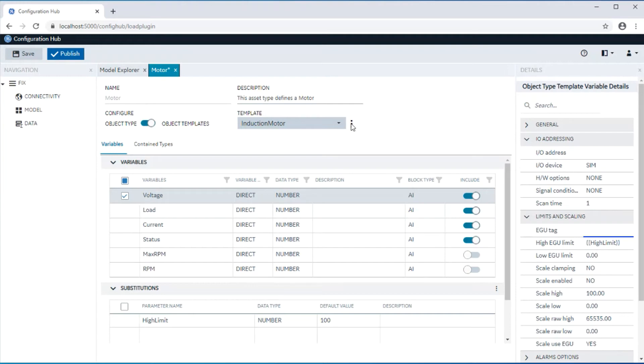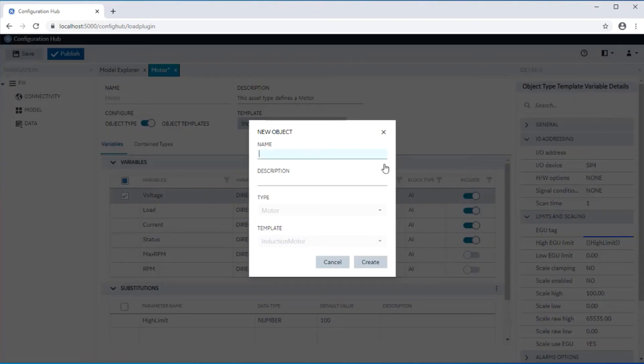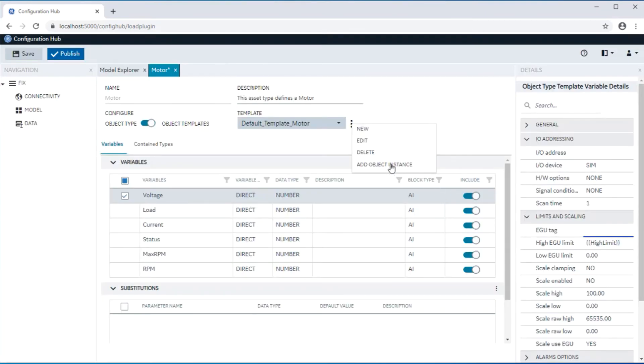After the type definition is complete, these types can be instantiated against a template to create an asset instance. In this example, an asset instance is being created using the induction motor template, which creates variables that are included with the block type selected against the variables.